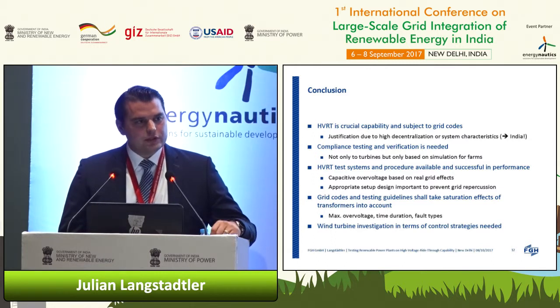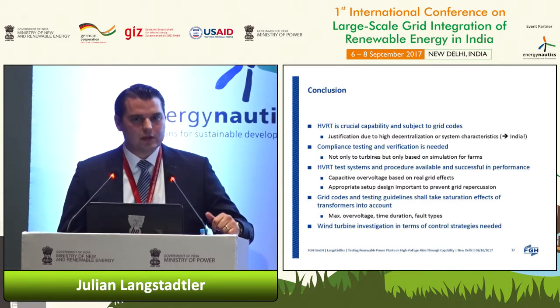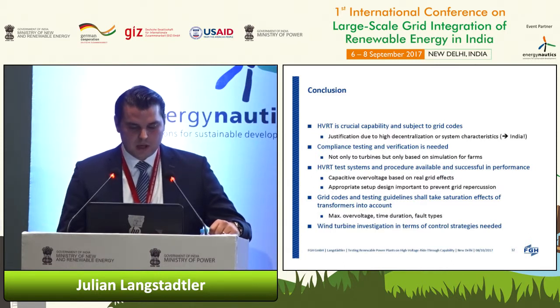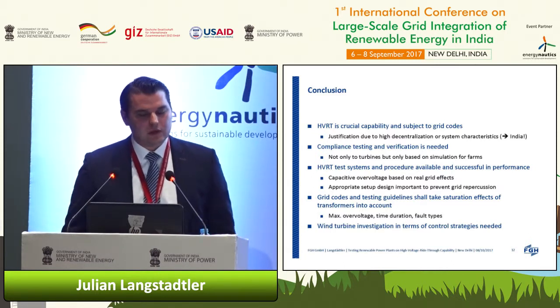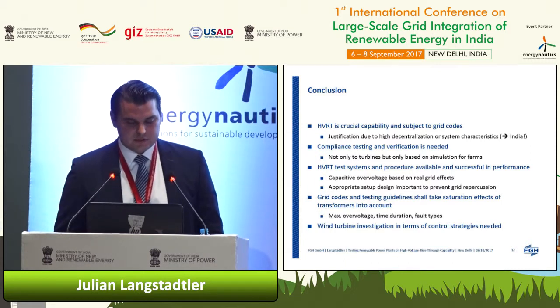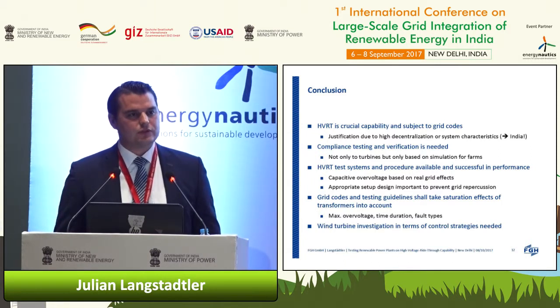For the grid code requirements, you should definitely take saturation effects into account. So don't come up with a requirement that says you must withstand voltages up to 170% of nominal voltage. It actually doesn't make sense, at least for the generators. There's always a transformer in between. And it is definitely also subject to investigation for wind turbines in terms of control strategies.